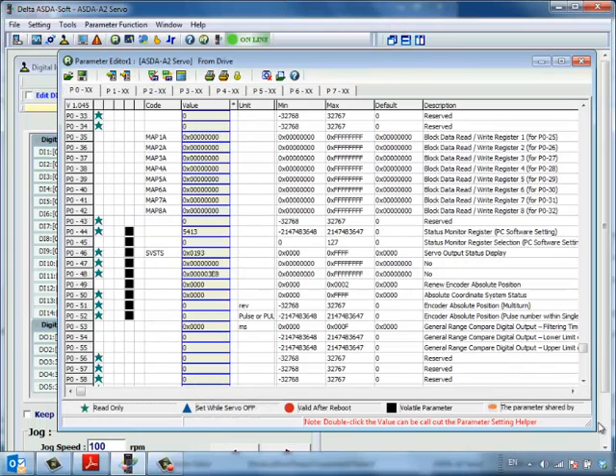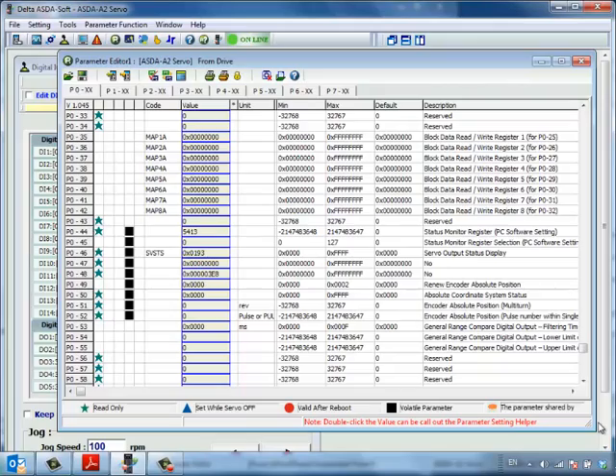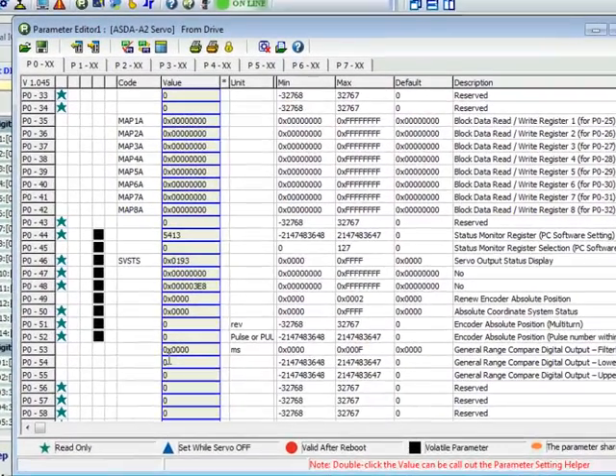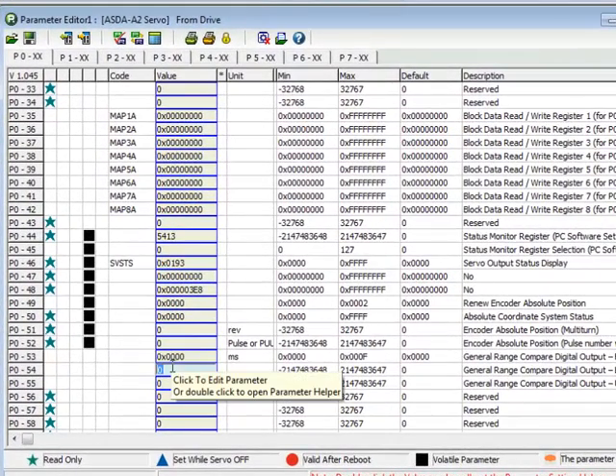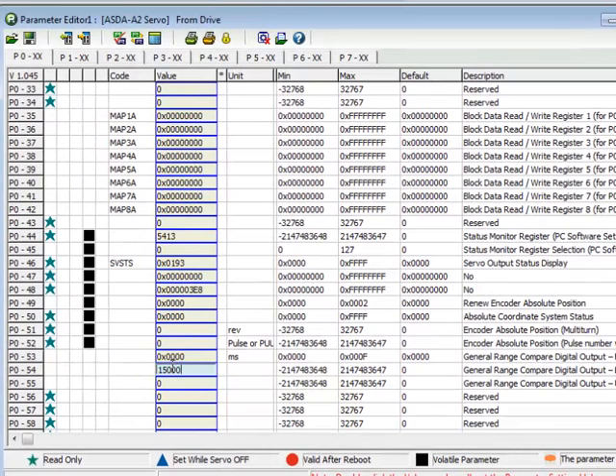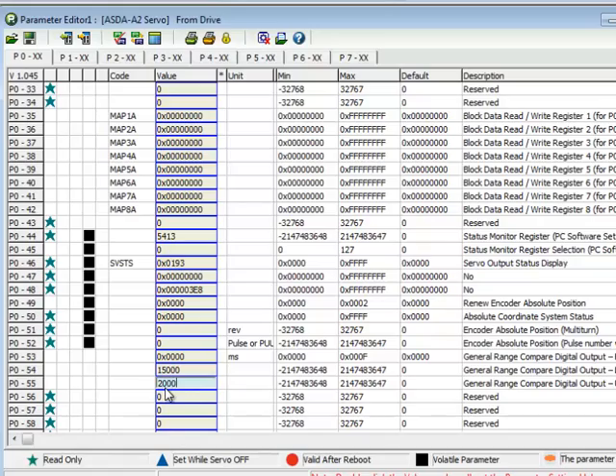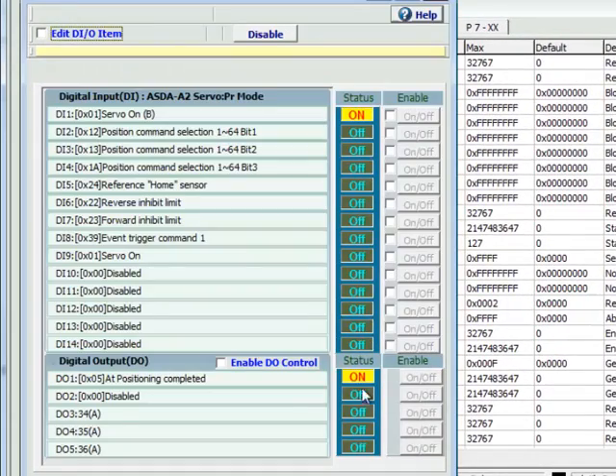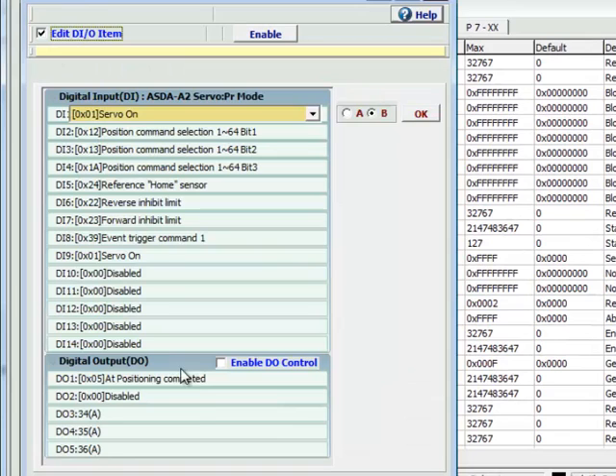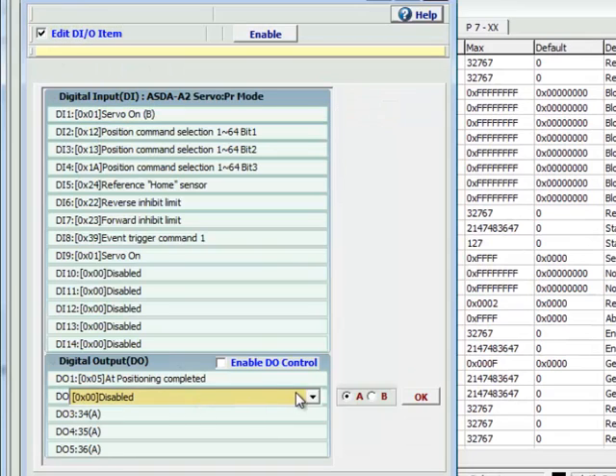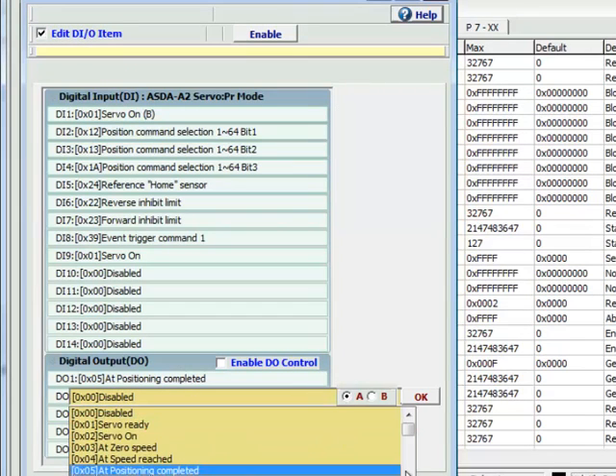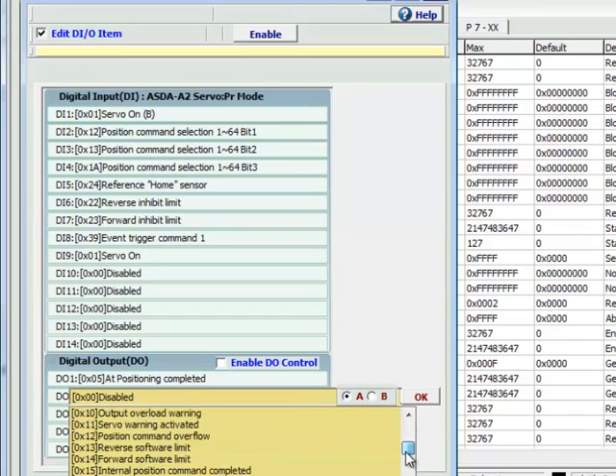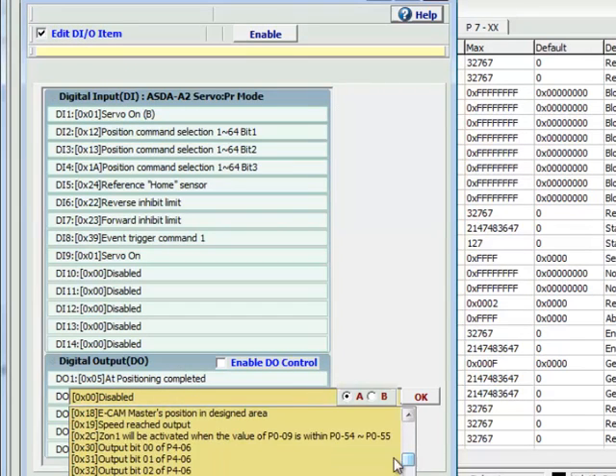You can also have an output fire within a given position window using the built-in zone compare function of the servo drive. Just set the position range you would like in P054 and P055. Then, configure a digital output to be used as your zone compare output.